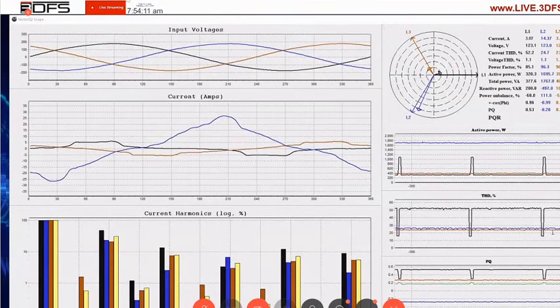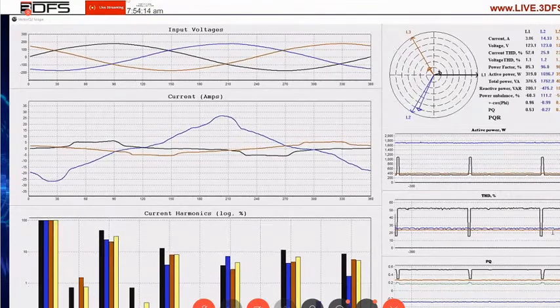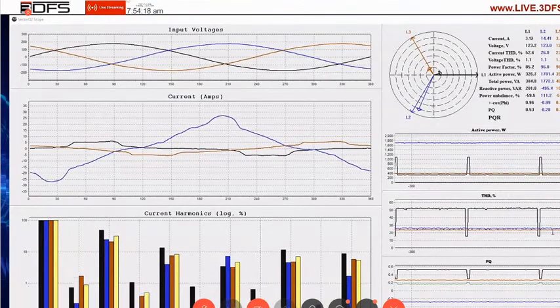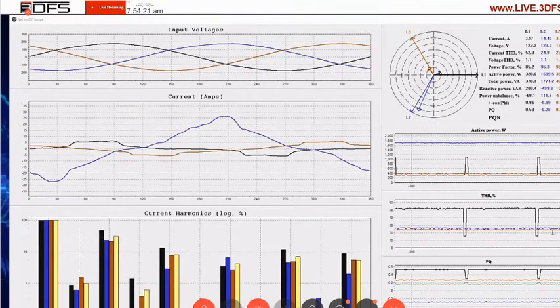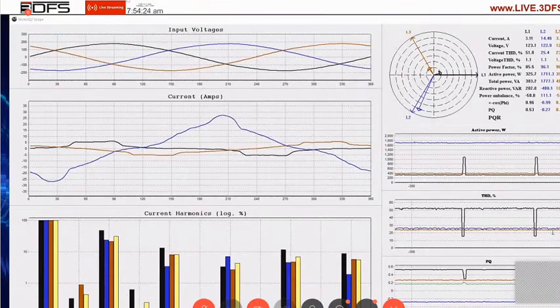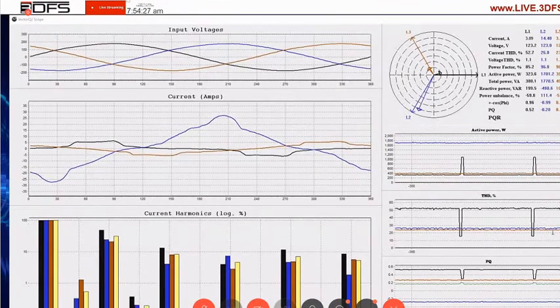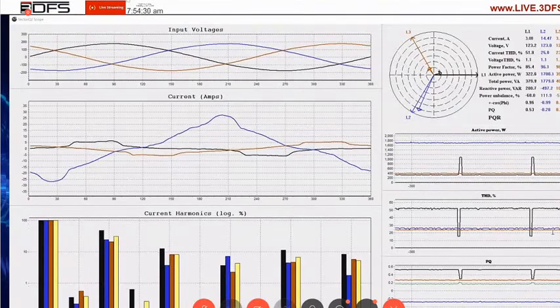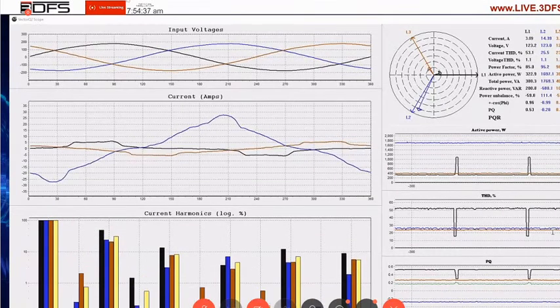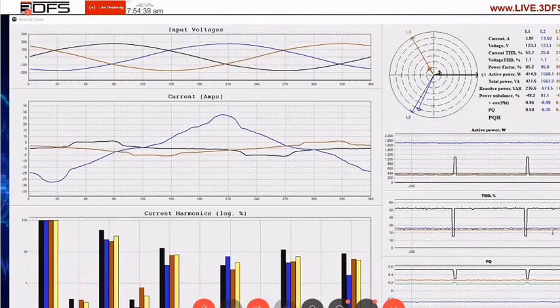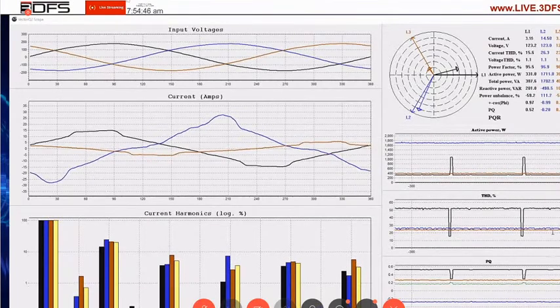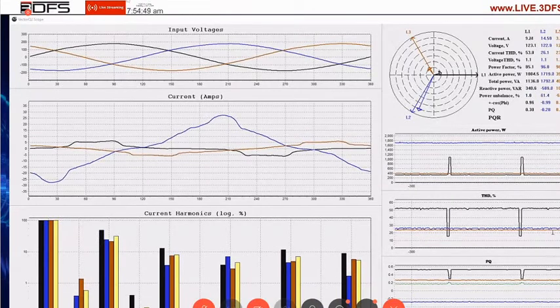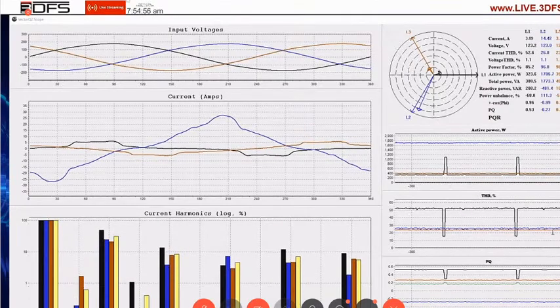And this is what we're delivering: precise electricity control in real time. The power capacity of a typical active harmonic filter can be divided between harmonic compensation, power factor compensation, and load balancing. So it's programmable. For a fixed, defined load, an active harmonic filter can probably handle the electrical part of what's being demonstrated, apart from predictive maintenance, since signature analysis doesn't exist in an active harmonic filter. That was my first question. My second question was, what would be the approximate loss in this system per kVA or per ampere?